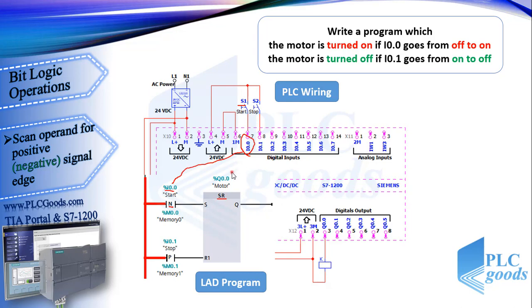When this pushbutton is in its normal condition, I 0.0 is 0. If I press it, I 0.0 will change from 0 to 1. Then if I release the start pushbutton, I 0.0 state changes from 1 to 0. Now the used instruction generates a pulse for just one program cycle, and this pulse makes the SR flip-flop turn on its output.